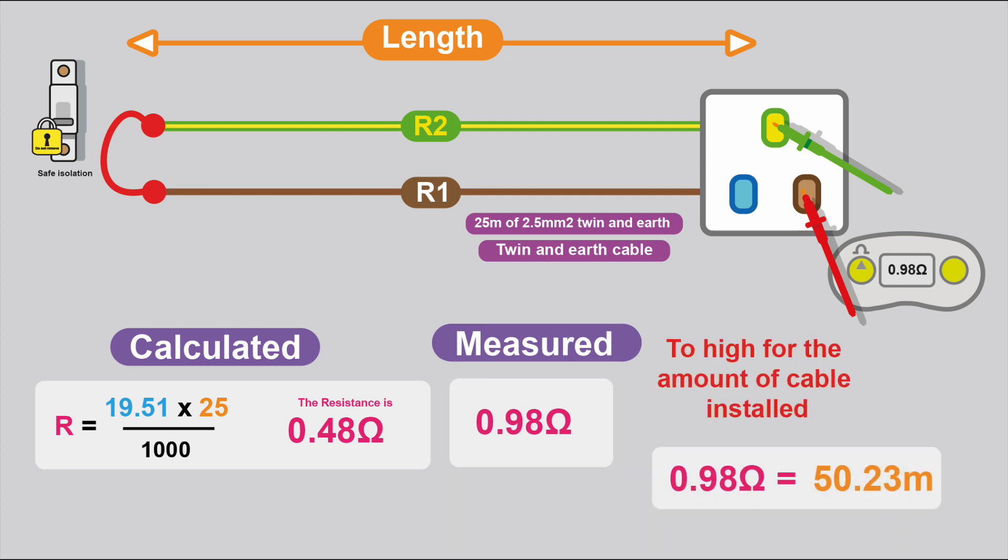The reason why it's useful to compare it to the calculated version is that you're verifying your actual test result. Say if your measured reading was 0.98 of an ohm, that would equate to over 50 metres of cable, and you know that you put around about 25 metres in. So that's well out, so you need to do some further investigation.